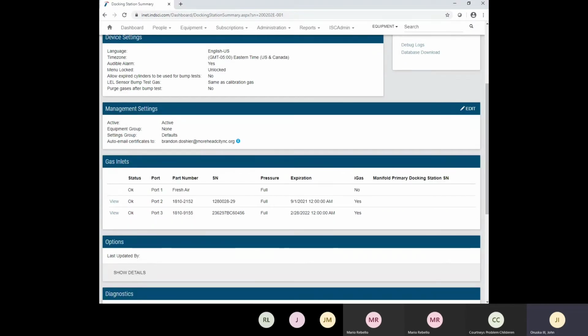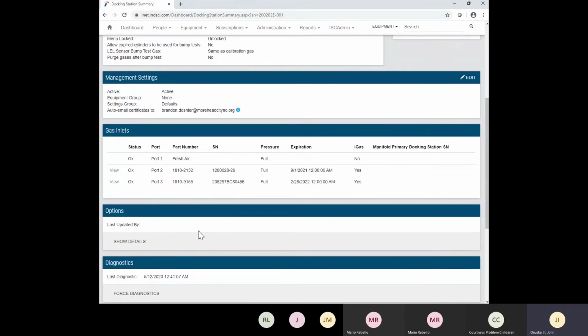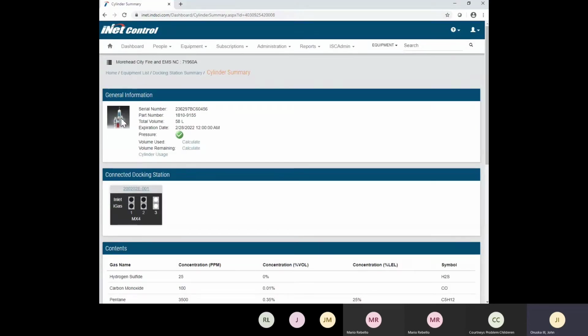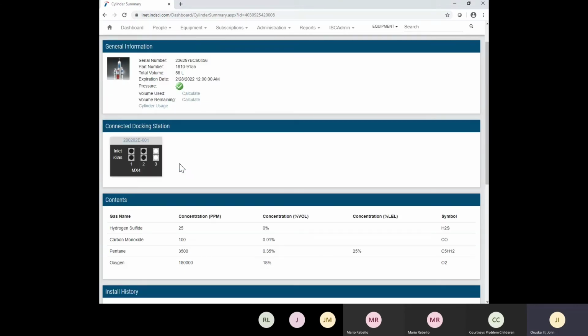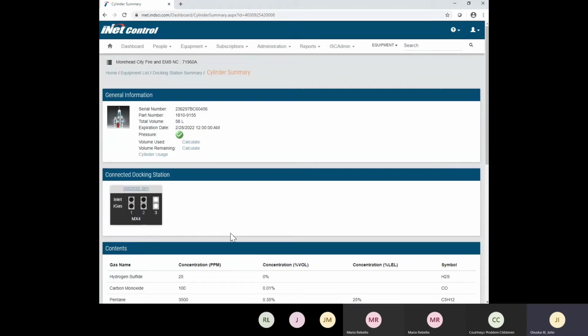And then whenever I come down here, I can see here's my gas bottles that are hooked up, and it shows that the pressure is full. And if I actually click on view, let's go to this one right here, I can see, okay, here's when it expires, here's all the information with it, and what concentrations are in it. So this is your 4-gas bottle right here. And if I click on calculate right here, it's going to show me how much of the gas has already been used. So this is a 58-liter cylinder, and it's already used 2.46 liters out of that whole bottle.